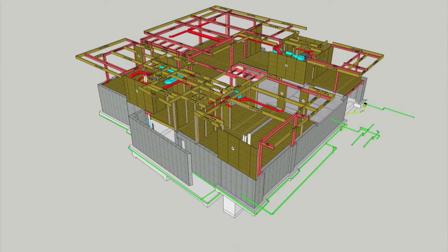We had to make a few modifications to the design. In one area the ductwork ran through a skylight, there are shear penetrations to review, ceiling heights compromised, and one area where the ductwork is above the roof. And the key here is, we know these issues exist, and so they can be worked out long before you get to that point in the construction of the project.